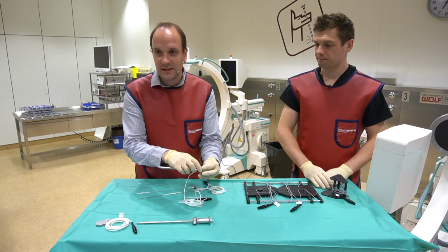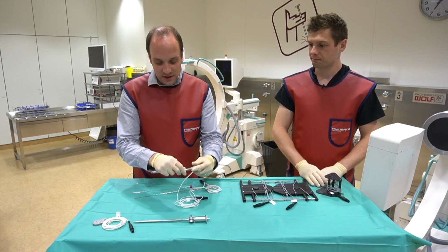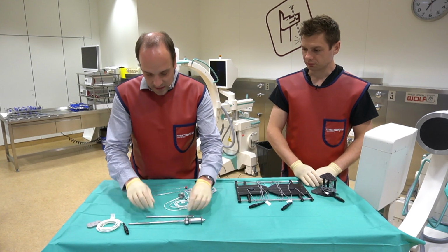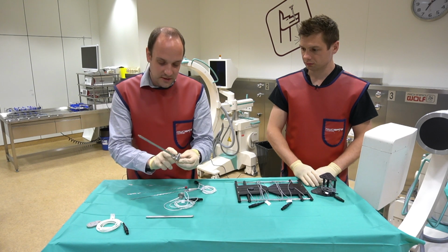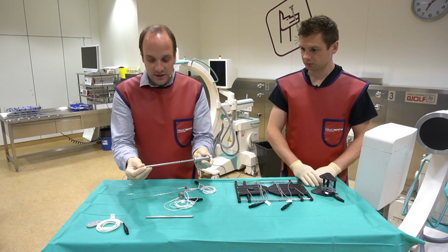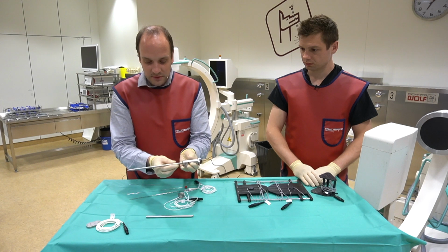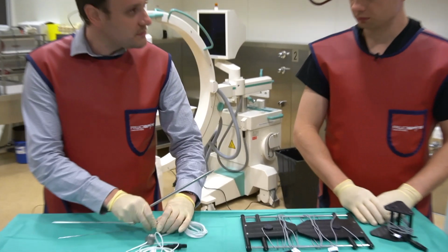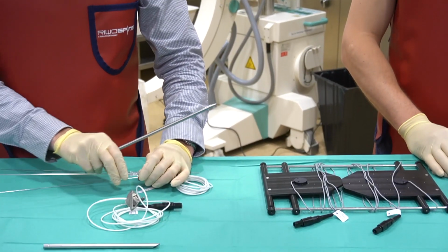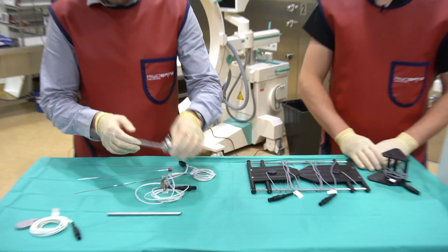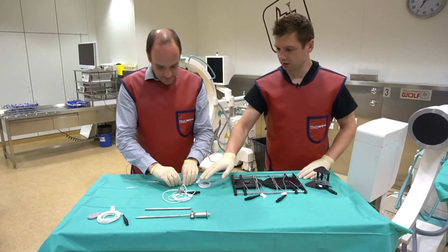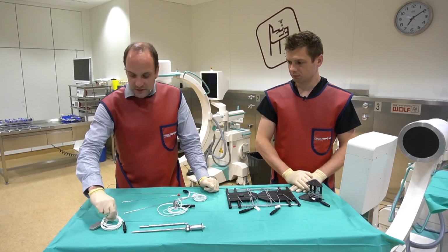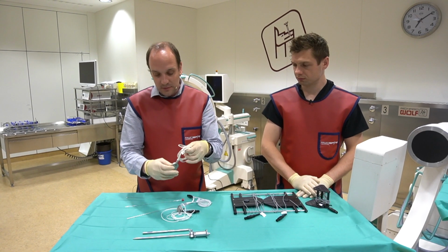And inside this handle, we have the sensors that are making it possible to trace the position of the working sleeve. Further, here we have an adapter to the regular 7 millimeter dilator, into which we can also place the same sensor which we've used before to track the needle, to track the dilator later. So we can track the needle, the dilator, and exactly, the sleeve.